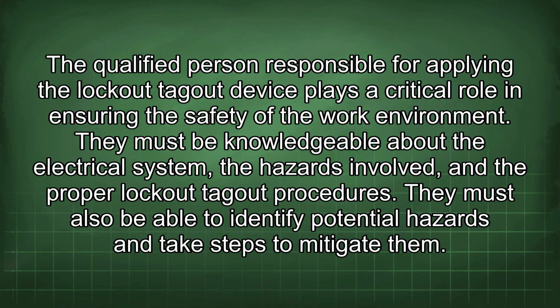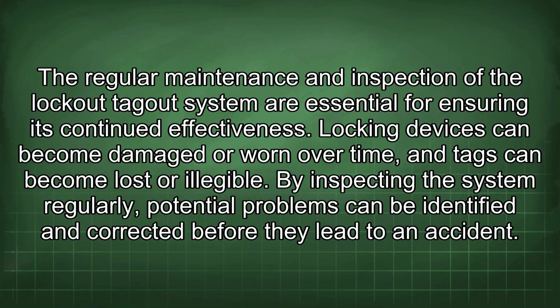The qualified person responsible for applying the lockout tag-out device plays a critical role in ensuring the safety of the work environment. They must be knowledgeable about the electrical system, the hazards involved, and the proper lockout tag-out procedures. They must also be able to identify potential hazards and take steps to mitigate them. The regular maintenance and inspection of the lockout tag-out system are essential for ensuring its continued effectiveness. Locking devices can become damaged or worn over time, and tags can become lost or illegible. By inspecting the system regularly, potential problems can be identified and corrected before they lead to an accident.